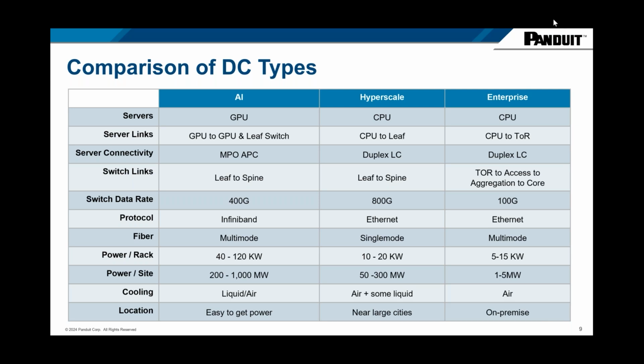So we're not talking about 150 watts per square foot, we're talking kilowatts per cabinet, significantly higher. You start adding that up at a cabinet level, then look at facilities - we're talking about facilities moving from 1 megawatt, which used to be considered big, to 5. Folks are bringing on 100 megawatts, 300 megawatts to help support this. I believe a lot of that's for the training portion, but it's coming fast.